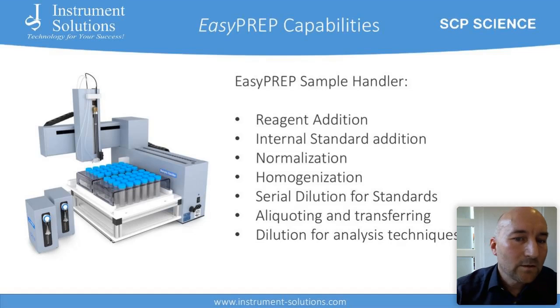So the main capabilities of the EasyPREP sample handler are reagent addition, adding internal standards, normalization by using an ultrasonic level sensor, homogenization by using a bubble stirrer, that can do serial dilutions for your standards, do general aliquoting and transferring of inorganic liquids, and also used for any types of dilution of analysis techniques. It's freely programmable, so you can use every rack that you want on the EasyPREP.